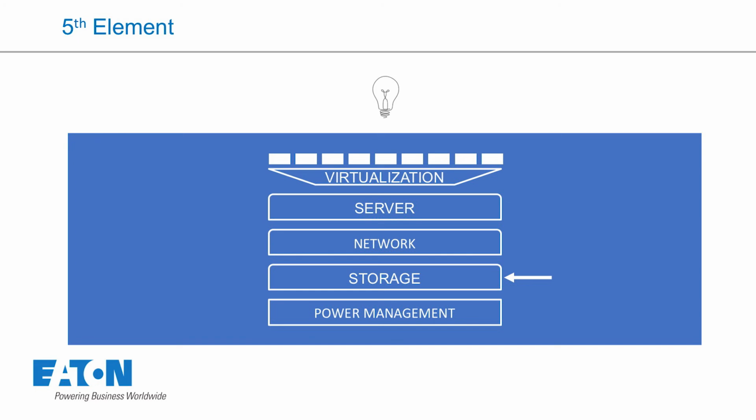We're migrating this data towards the cloud, and at the same time, power capping or turning off these network devices in a rack. And that'll extend it: instead of 15 kVA for 5 minutes, you can support 15 kVA for 10 minutes, 8 minutes.